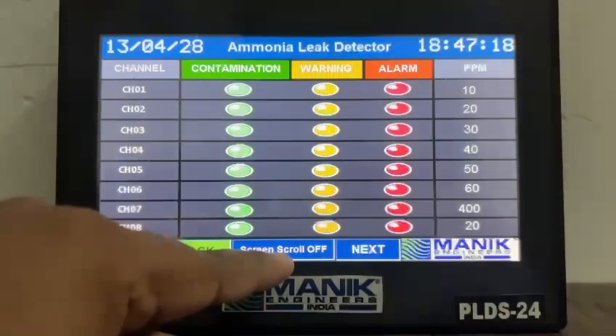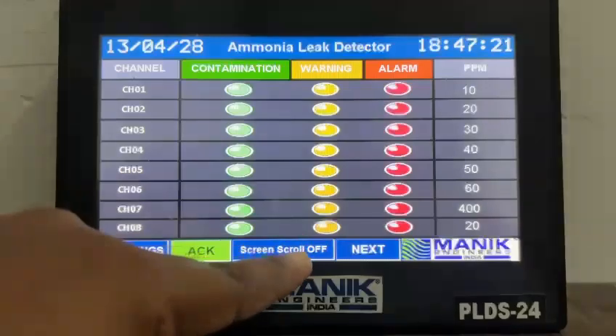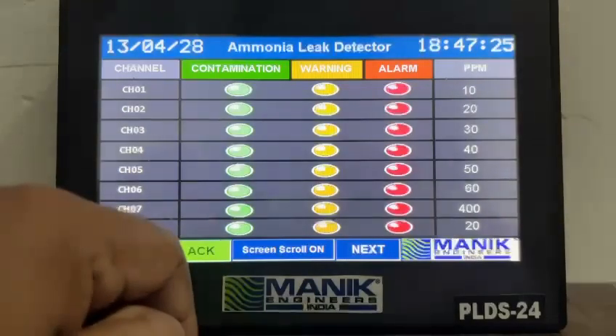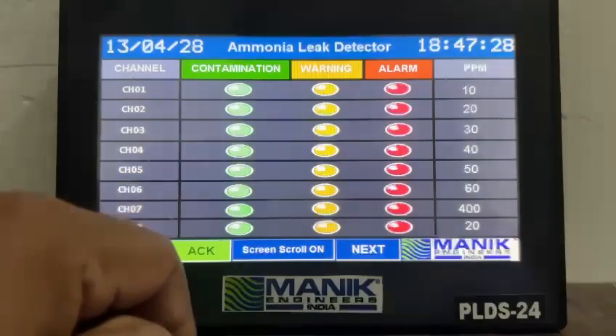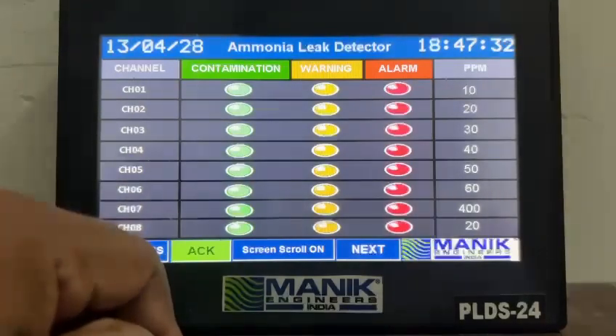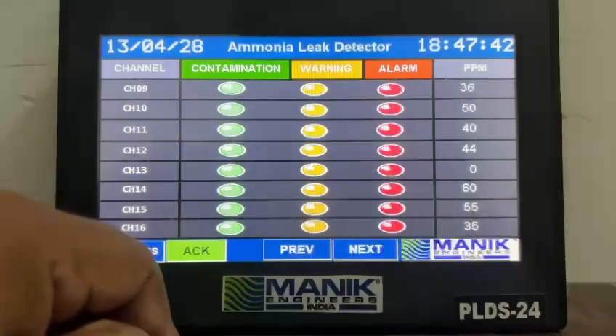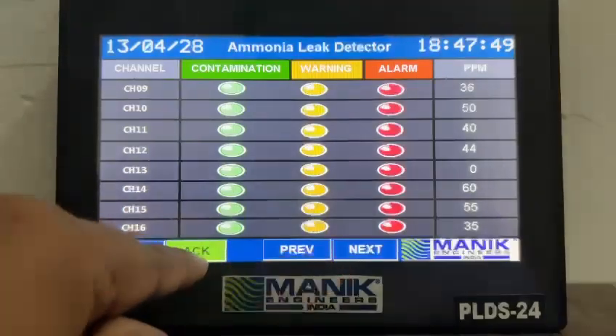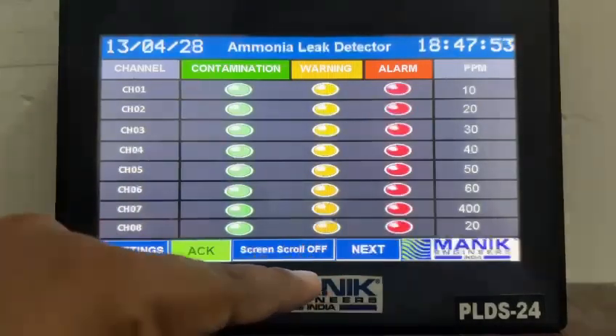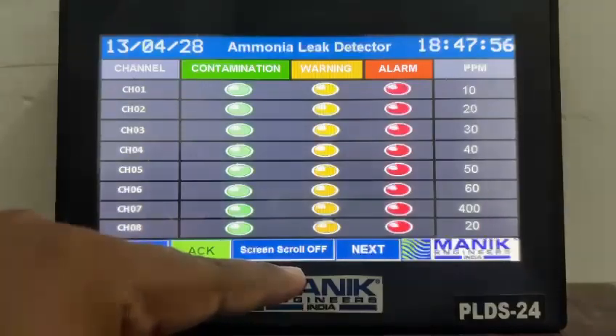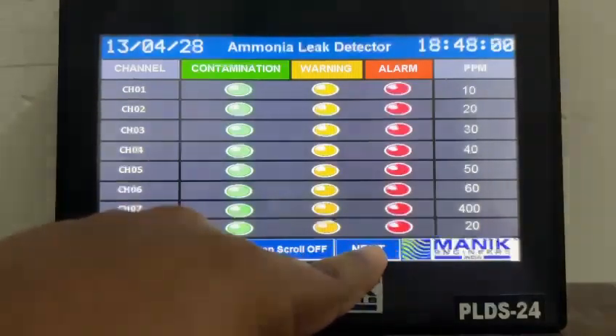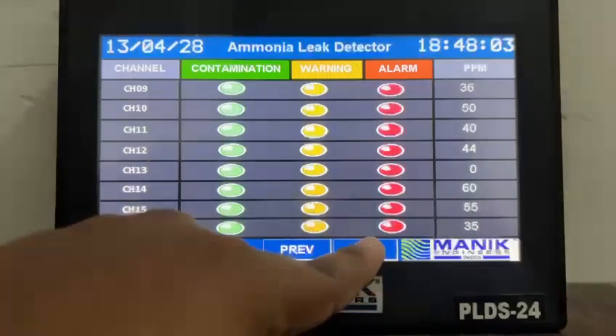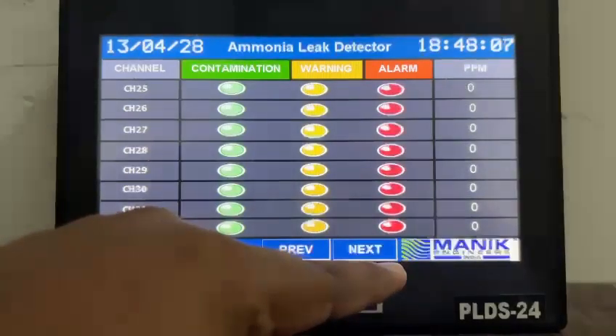So for screen on and off operation, just tap on the screen off button, then the screen on operation will start. The screen on operation is for channel number 1 to 32. We have 4 screens, which rotate sequentially from screen 1 to screen 4: channel number 1 to 8, 9 to 16, 17 to 24, and 25 to 32. Also, we have a next button available to manually scroll our screen. So just tap on the next button. So we get the 9 to 16 channels, 17 to 24 channels, and 25 to 32 channels.